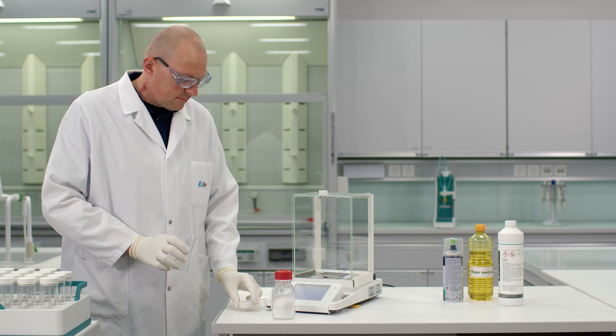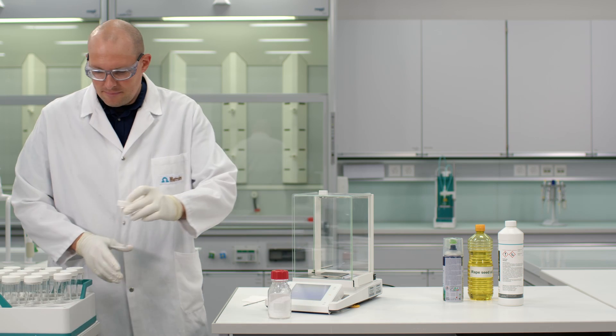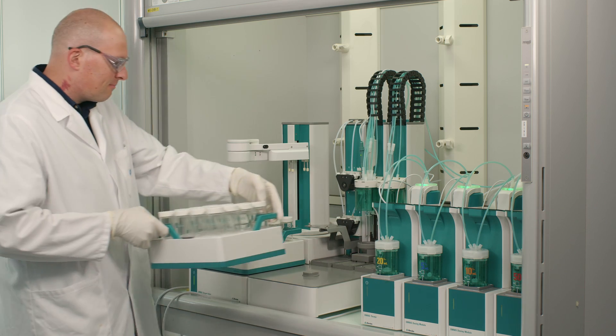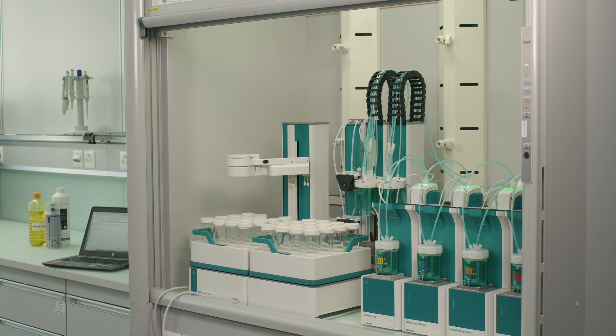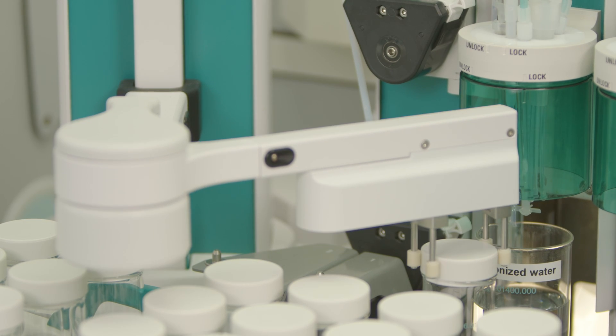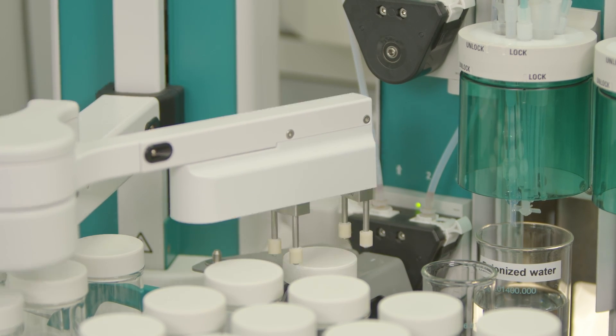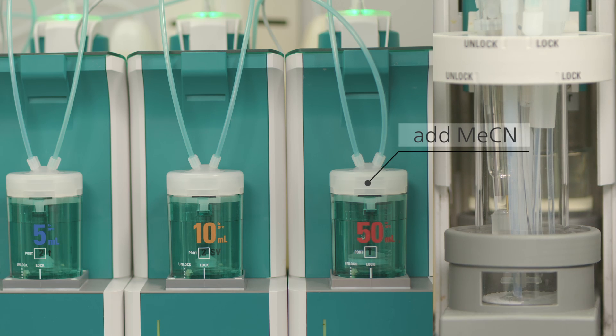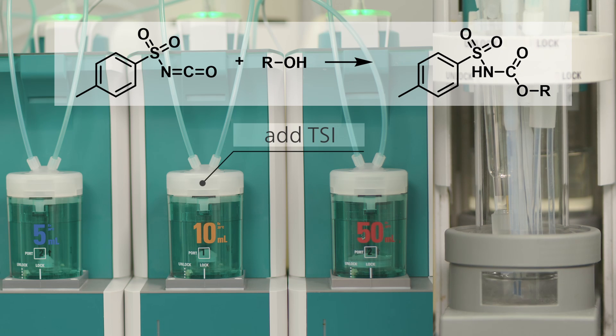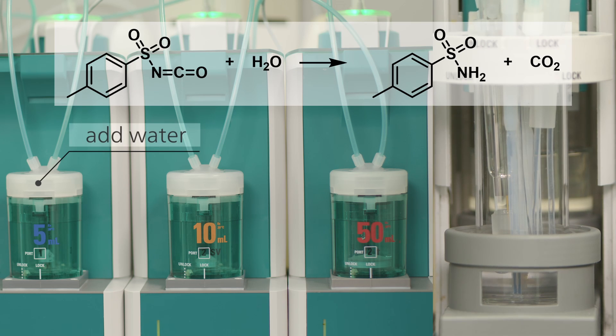The sample size depends on the expected hydroxyl number of your sample. Then you only bring the sample rack to the Omnis sample robot. Start your method and the beaker is brought to the workstation. You should use covered beakers, as additional moisture can falsify your result. TSI is added, which reacts with the hydroxyl groups of the sample to form an acidic carbamate. Water is added to convert the excess TSI to sulfonamide, so it won't interfere with the titration.